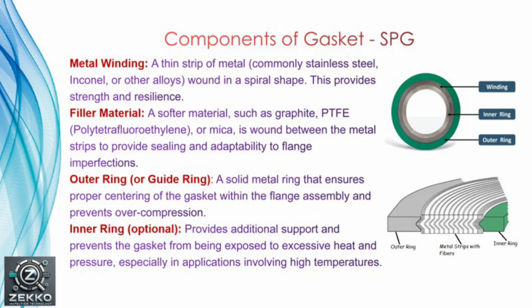Here now filler material is a softer material such as graphite, PTFE, polytetrafluoroethylene, or mica. It is wound between the metal strip to provide sealing and adaptability to flange imperfections. Then there is an outer ring or guide ring. It is a solid metal ring that ensures proper centering of the gasket within the flange assembly and prevents over compression. The last one is inner ring, and that is optional. It provides additional support and prevents the gasket from being exposed to excessive heat or pressure, especially in applications involving high temperatures.